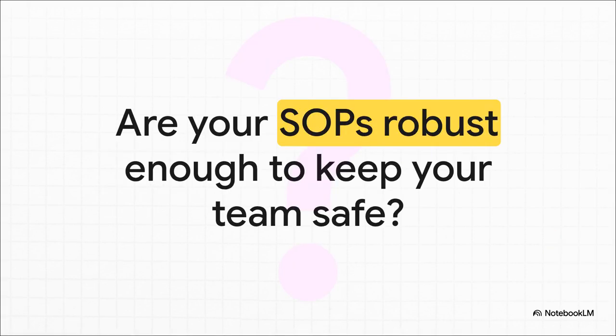And that brings us to our final thought for this explainer. The entire industry is abandoning non-flammable gases like R22 and R410A. It's no longer a matter of if you'll encounter these flammable systems, but when. So the question you really need to ask yourself today is this: are your standard operating procedures truly adapted to handle the explosive risks of tomorrow's refrigerants? Take this knowledge, update your SOPs, and make sure every single technician comes home safe.